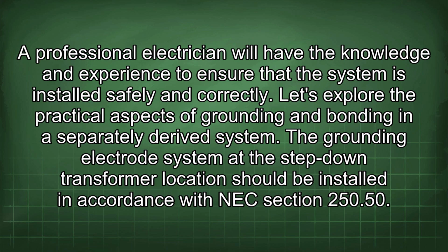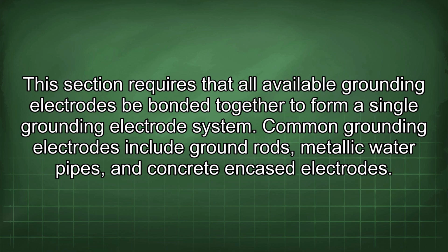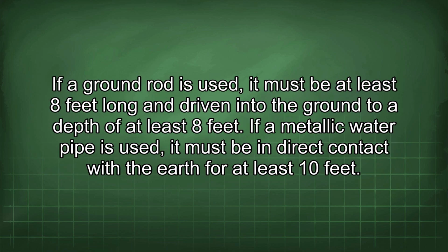Let's explore the practical aspects of grounding and bonding in a separately derived system. The grounding electrode system at the step-down transformer location should be installed in accordance with NEC section 250.50. This section requires that all available grounding electrodes be bonded together to form a single grounding electrode system. Common grounding electrodes include ground rods, metallic water pipes, and concrete encased electrodes. If a ground rod is used, it must be at least 8 feet long and driven into the ground to a depth of at least 8 feet.